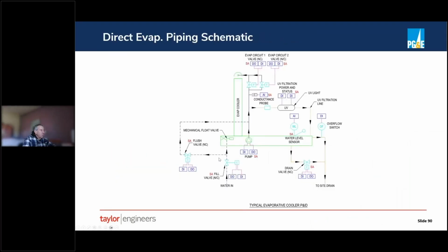There's a waterside to direct evap, right? You need to keep water flowing over the media when you want it to be operating. So here's a simple schematic of a sump. It's common to have one sump per air handler. You can also have a sort of remote gang sump that serves all the air handlers, but this would be a schematic for one air handler, right? You've got a sump here. That's this sort of green box. You have a float valve to fill up the sump.